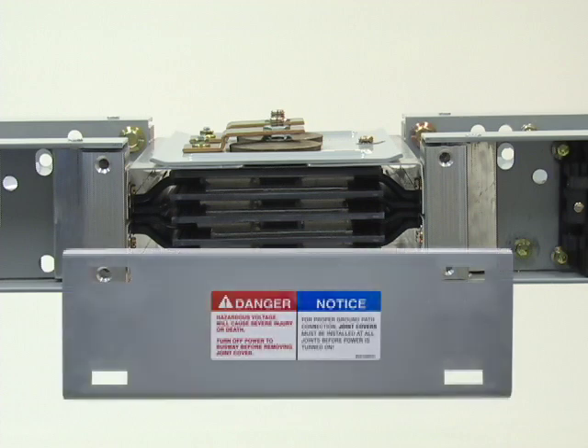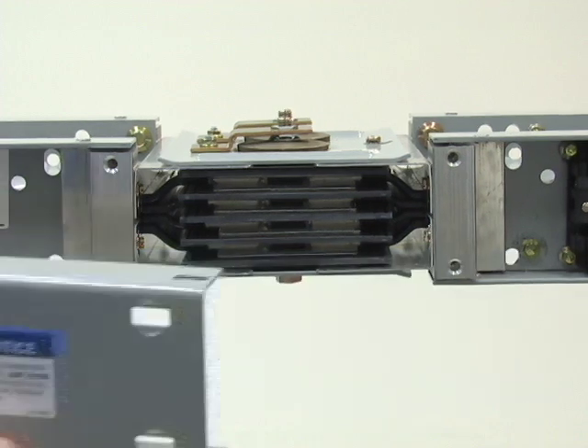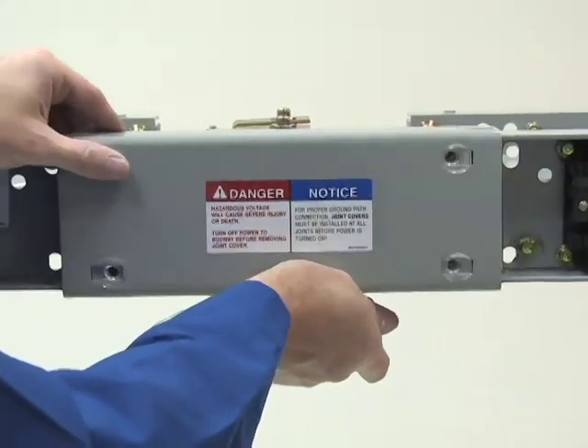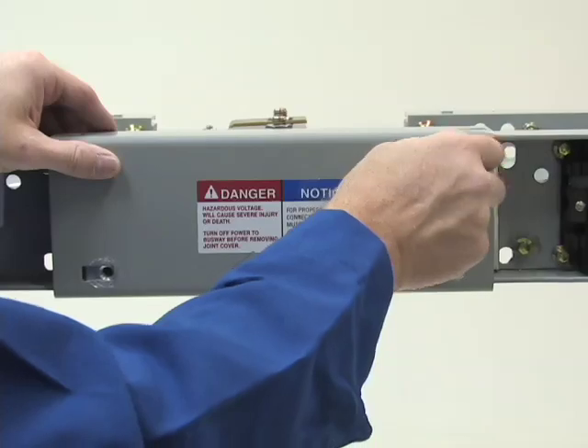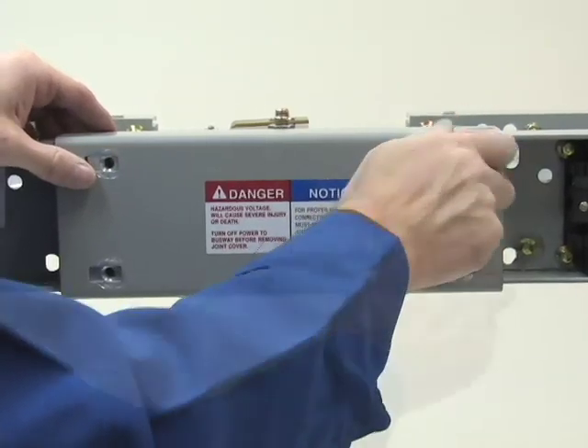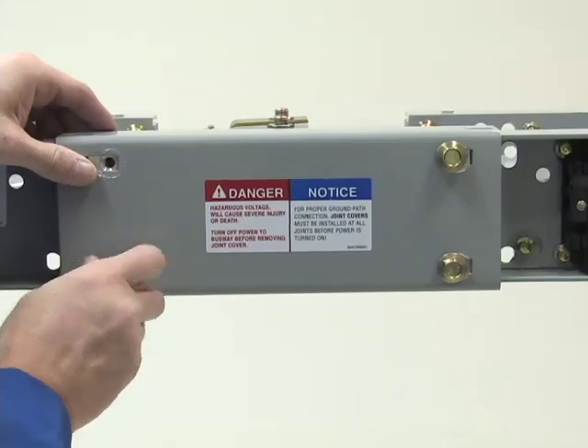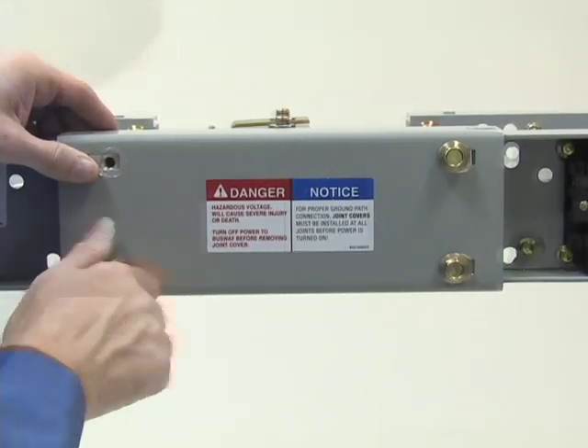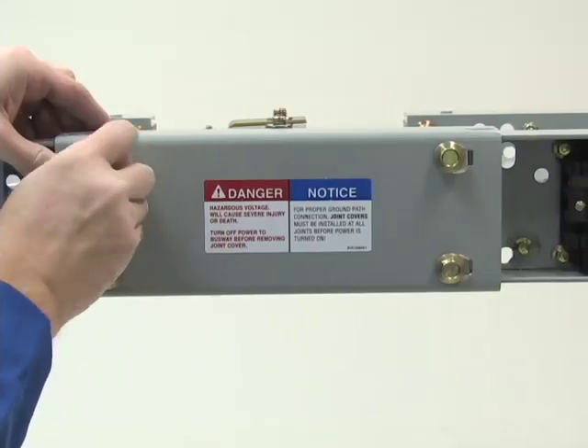Joint covers prevent incidental contact with energized conductors and connect a portion of the housing ground path between two sections of busway. To begin installation, attach the joint cover to the busway with the flanged head hex bolts provided to the extruded end blocks of the busway, making sure the contact surfaces of the end blocks and the inner side of the joint covers are clean.